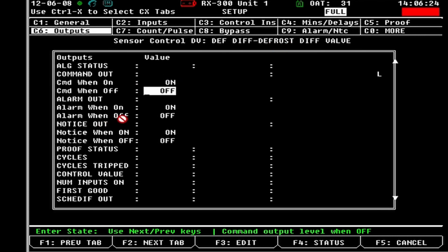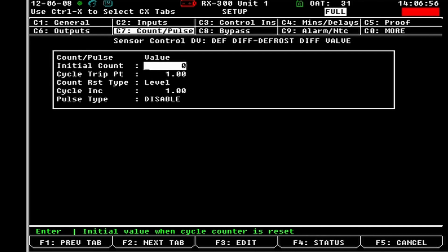So same thing with alarm. You could put not active in here. The newer versions is none. Same thing with notices. And then all these points down here, the cycles, trip, control value, just like the analog sensor control, that's going to be your loggable points. That's going to be if you're using the counting feature and you're actually counting how many times something cycles and all that. So we move on to the next tab, which is going to be the count and pulse.